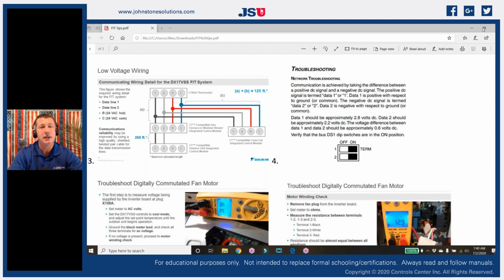I use Climate Talk a lot in our commercial industrial communicating equipment. All the CPC products, we're using a 5-volt DC signal. So what we're really doing is using a positive and a negative DC signal, and it's communicating back and forth all of its commands. It's very simple to understand what it's doing from a troubleshooting aspect.